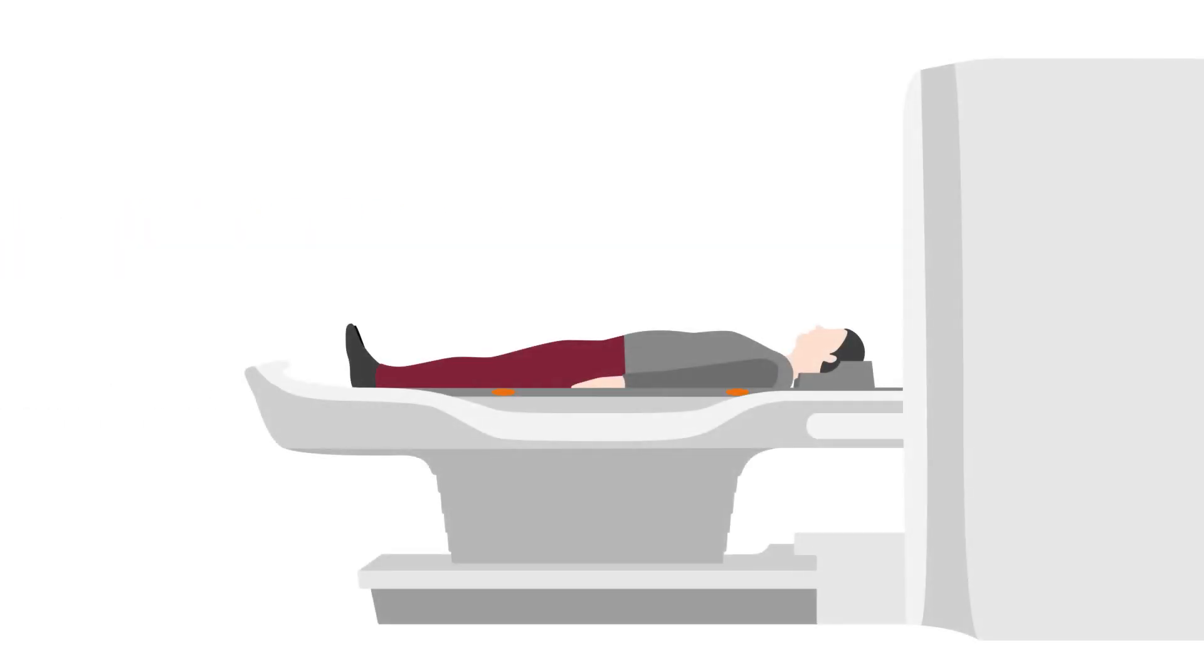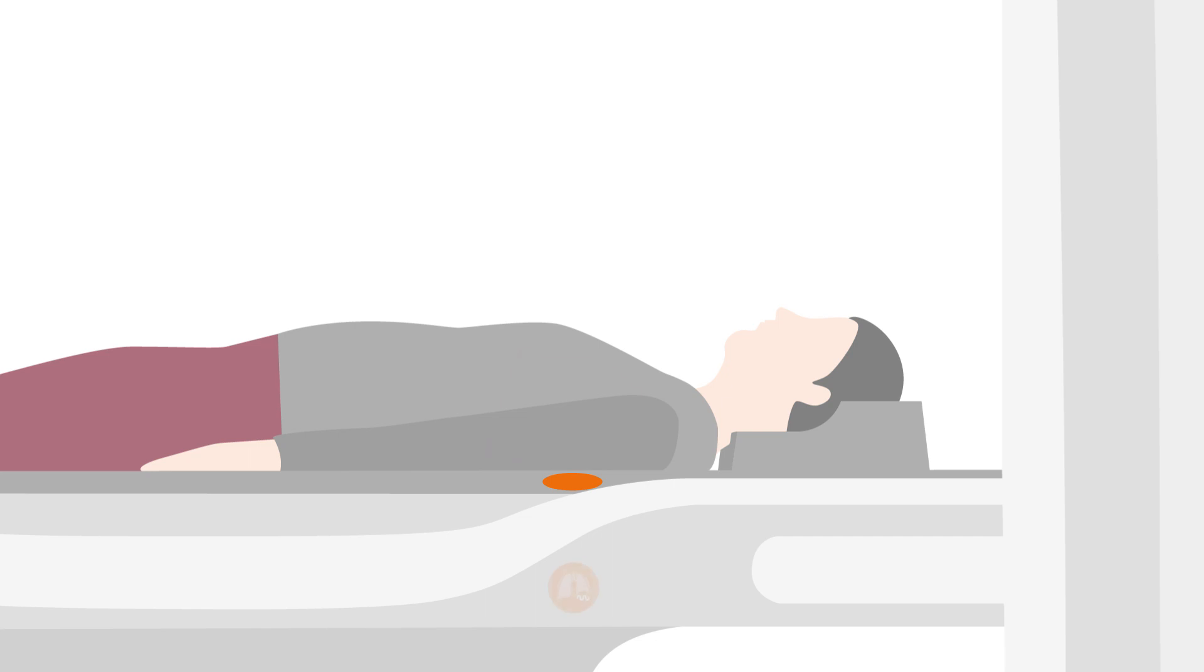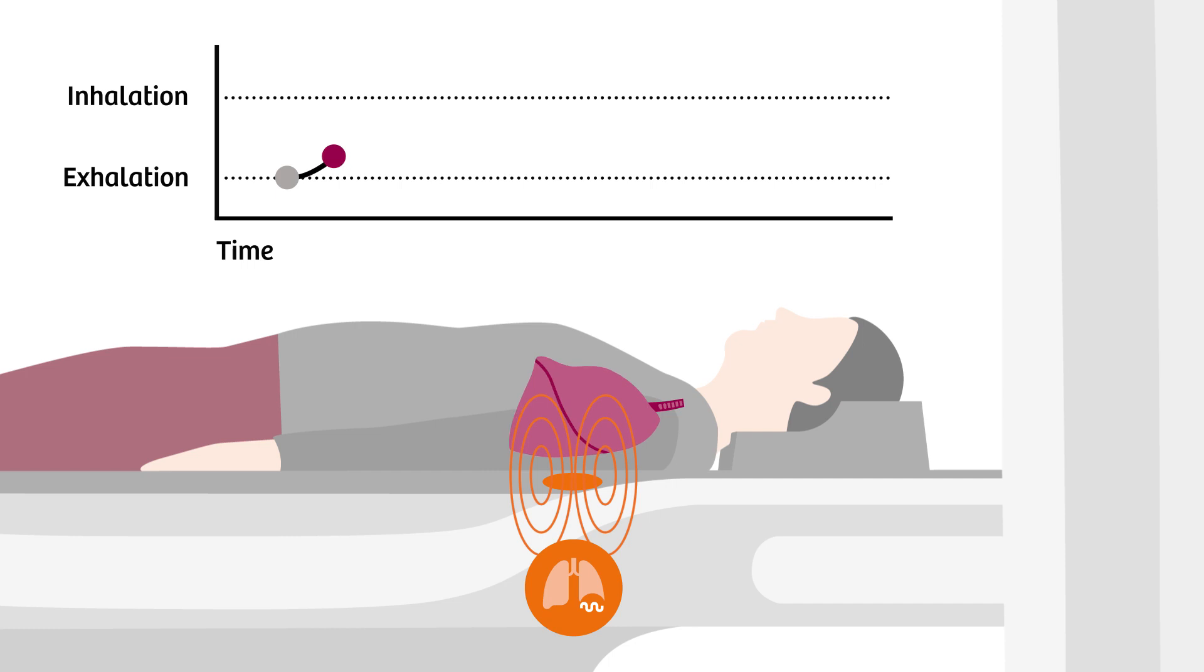Two respiratory sensors are embedded in the spine coil, one for headfirst and one for feet first exams. The sensors produce a local magnetic field that is affected by moving tissue from the changes of the lung volume.